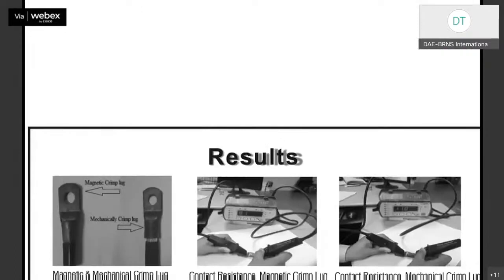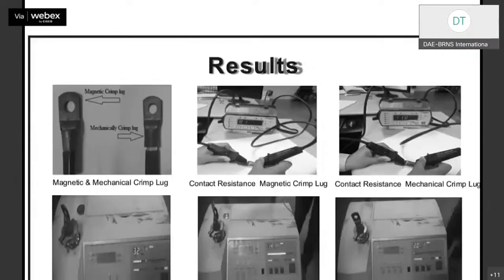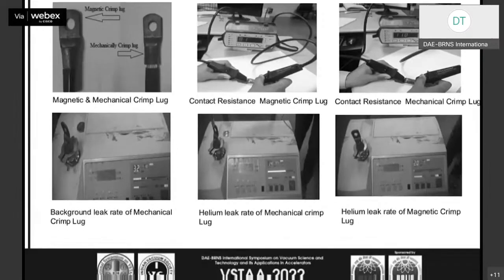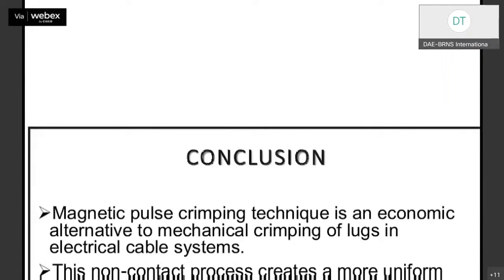Here the crimping is of copper lug to the strands of the conductor. This technique is very useful in terms of the connection, that is contact resistance, and uniform compression of the lug with the conductor of the cable takes place. Another advantage is that there are no marks on the surface of the connector, which is normally seen in conventional mechanical crimping. The contact resistance gets reduced, which is a very important parameter.